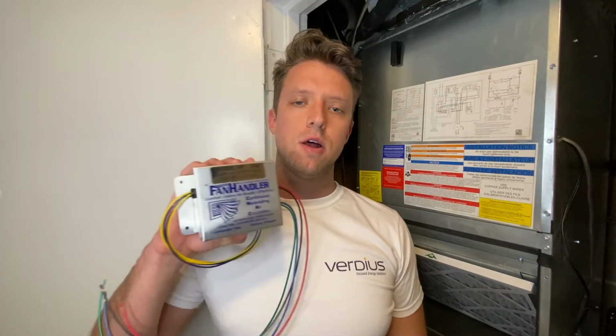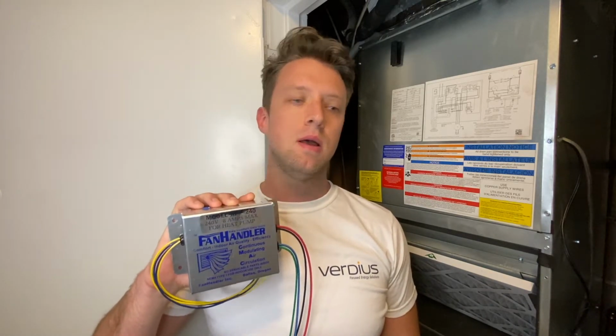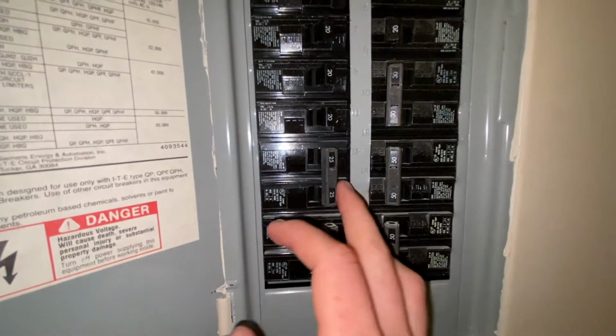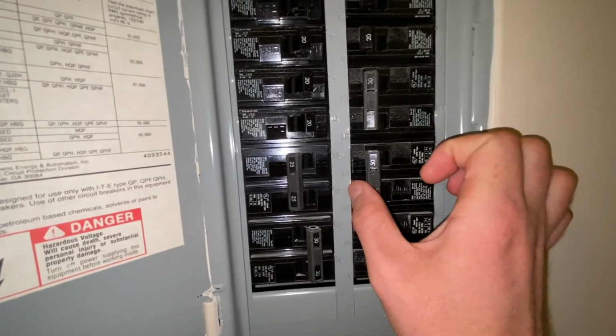Today we're going to be installing the fan handler continuous modulating air system on this heat pump evaporator. The first thing we want to do is turn off power to the evaporator and the condenser, so that's the inside unit and then the outside unit as well.